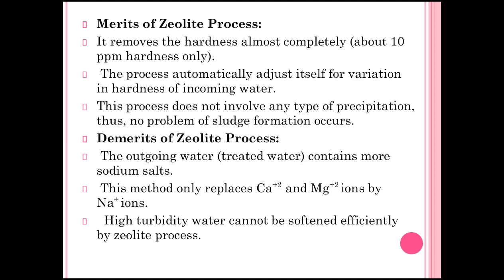Advantages and disadvantages of the zeolite process — Advantages: it removes hardness almost completely (about 10 ppm hardness only remains); the process automatically adjusts itself to variations in hardness of incoming water; this process does not involve any precipitation, so there is no problem of sludge formation. Disadvantages: the outgoing water contains more sodium salts; this method only replaces calcium and magnesium ions by sodium ions; highly turbid water cannot be softened efficiently by the zeolite process.